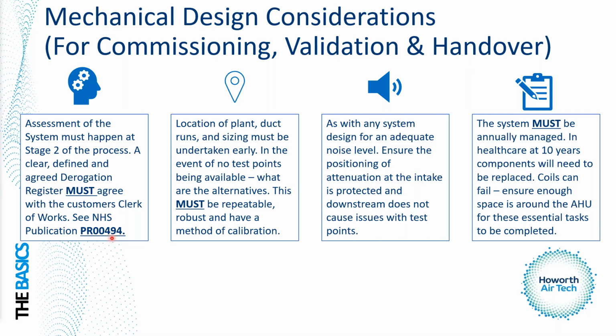The location of plant and duct runs is obviously an important one. In the early stages when the Revit models are being created, obviously we can size and adequately place ductwork. We're going to speak about that in a moment. But it's important that in those early stages the designer appreciates what's required within the ductwork. We have to put test positions in, which I'm going to show you in the next couple of slides.